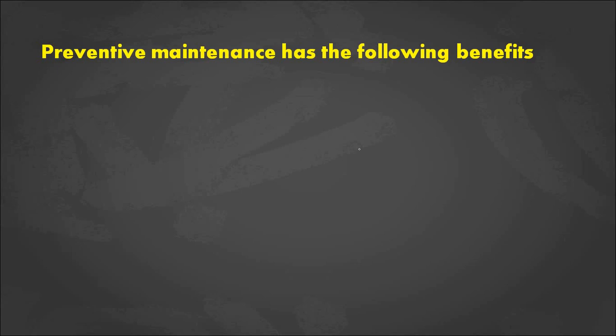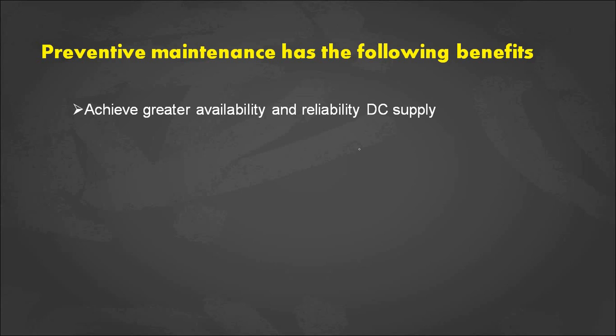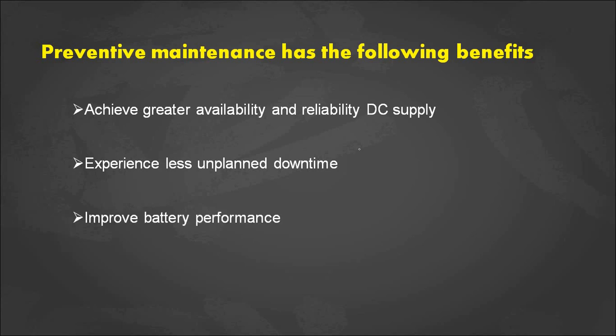So this preventive maintenance schedule has the following benefits. We can have greater availability and reliability of a DC supply, we can reduce the downtime, nothing but the shutdown time of a battery bank, and we can improve the battery performance. Thereby we can increase the life of the batteries. In order to have these benefits, we should maintain the batteries in a good healthy condition. That good healthy condition is possible by doing this preventive maintenance schedule.